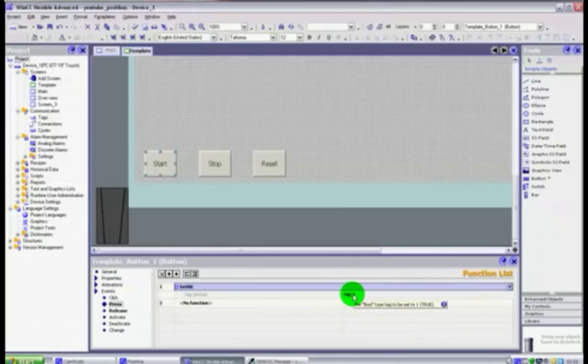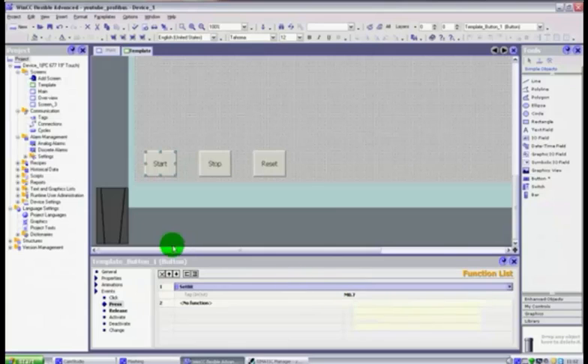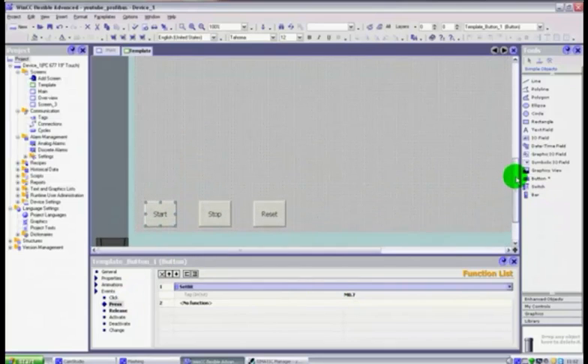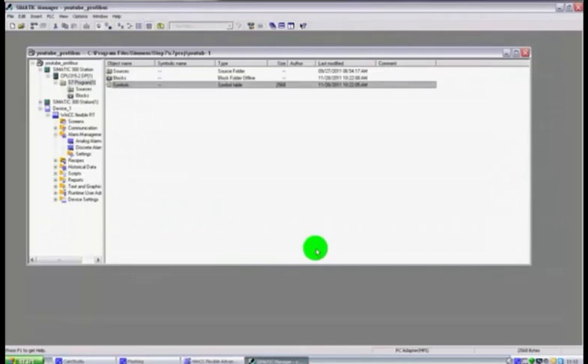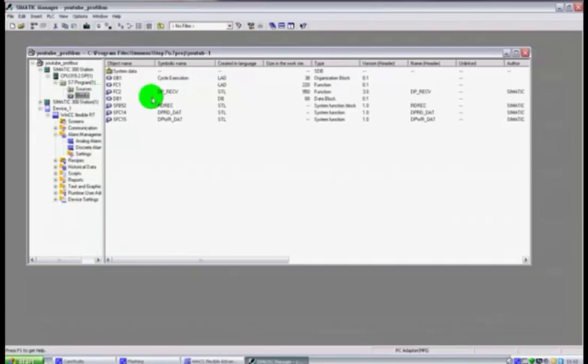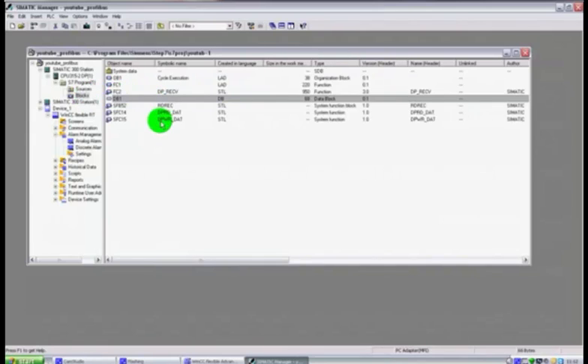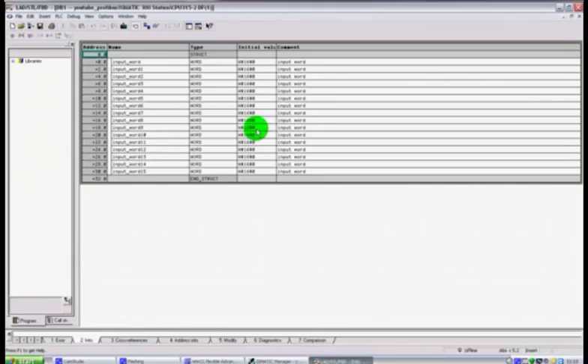So now when I press that button when we're in run mode with the HMI, whenever I press that start button it will set M0.7 for me and when I take my finger off the button it will reset it. And it will inform the PLC of that because of the connection. If you hover over things you will get a tooltip to tell you what it is. So that is simply how to access your symbol table. And just to prove the point, there's our station, there's our S7 program one and there's our symbol table. And our DB1 is there and if I opened up our DB1 you could see all of those words that we had access to. So there's all our words that we had.